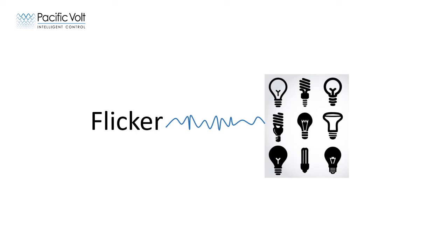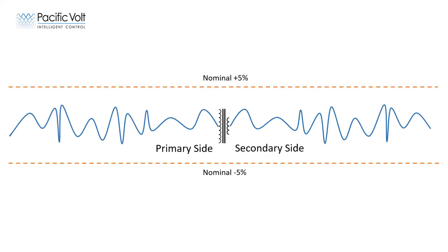We have now established that because of impedance, the voltage changes as the load changes, which brings us to the topic of flicker. Flicker refers to light intensity changing because the voltage is changing rapidly. Flicker is ultimately caused by large and rapid changes in load current. Flicker can originate on either side of the transformer.